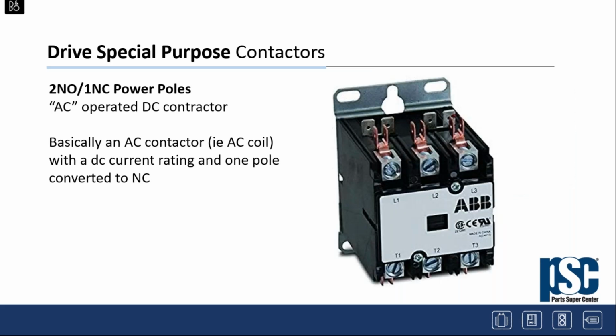I mentioned drive special purpose contactors. These are basically two normally open, one normally closed power pole. In this particular instance, this is an AC operated DC contactor, and this is very common for these drive special purpose devices. These devices are basically an AC contactor, i.e. it has an AC coil, but it has a DC rating, and one pole is converted on the 3-pole contactor from normally open to normally closed. So you have a 2 normally open, 1 normally closed power pole. And again, these are frequently found in a lot of package drives and small drive applications.